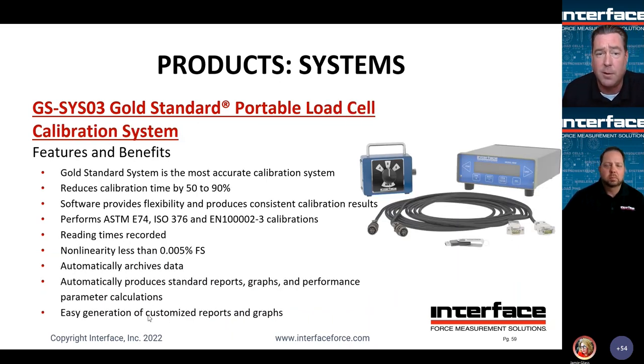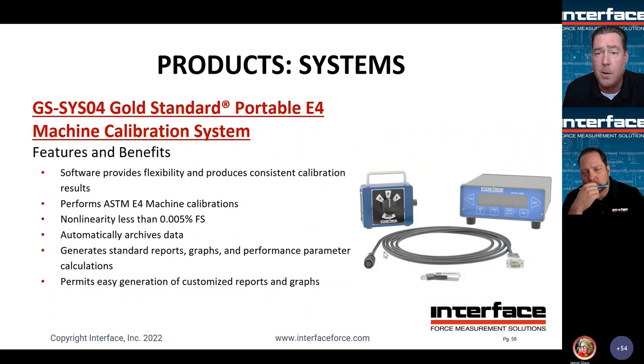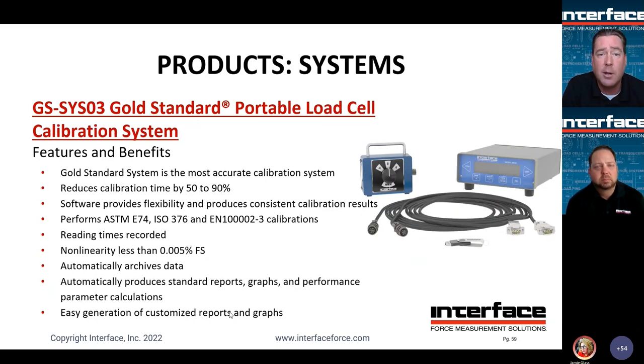So we consistently get feedback on E4 calibration about the benefits. One of the biggest benefits we hear about is the automatic report generation, I should say, and customization. It allows you to essentially have a one-click function where it's calculating performance of a calibration run. There's no hand calculation, and then customization of your calibration reports to fit your specific lab requirements. So we get good feedback on that a lot. And then next slide, thank you.